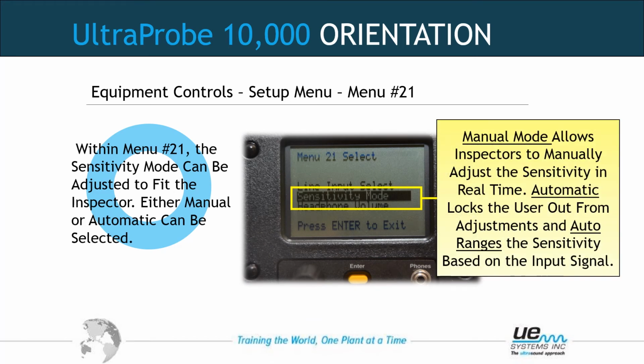Menu number 21, sensitivity mode. Not many use this. It automatically is supposed to adjust to the sensitivity needed for a recording and bring it into range. Most inspectors enjoy using the sensitivity and controlling that themselves. So it is either automatic or manual. It is defaulted to manual use.